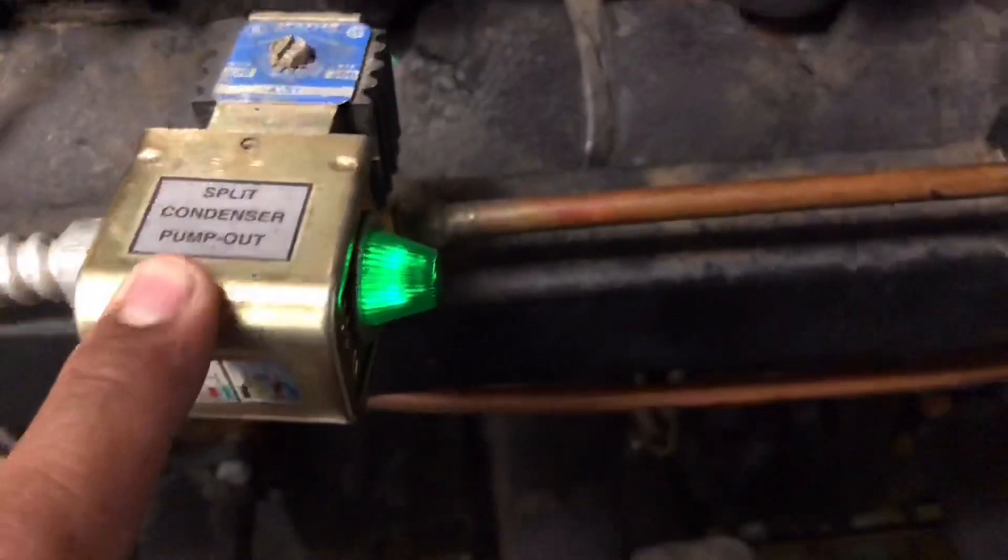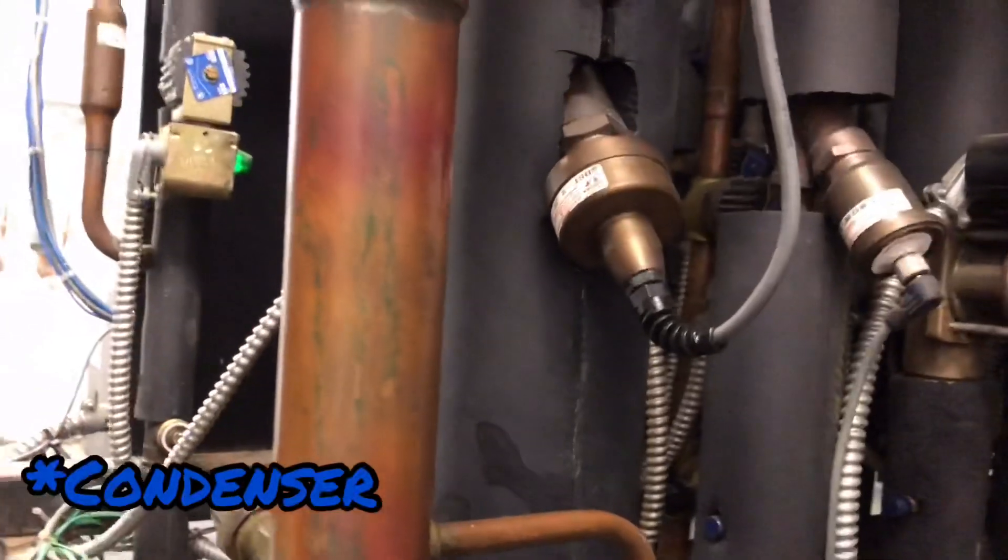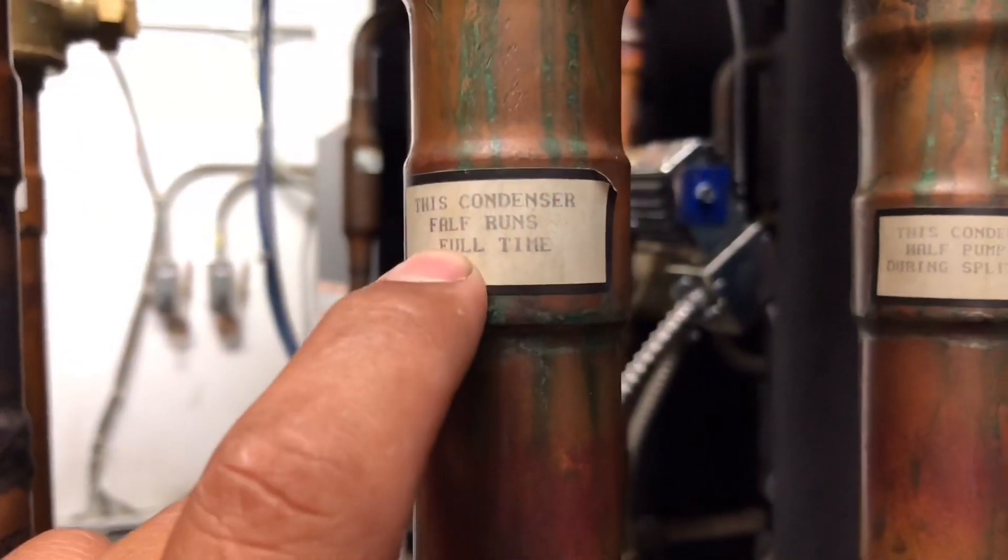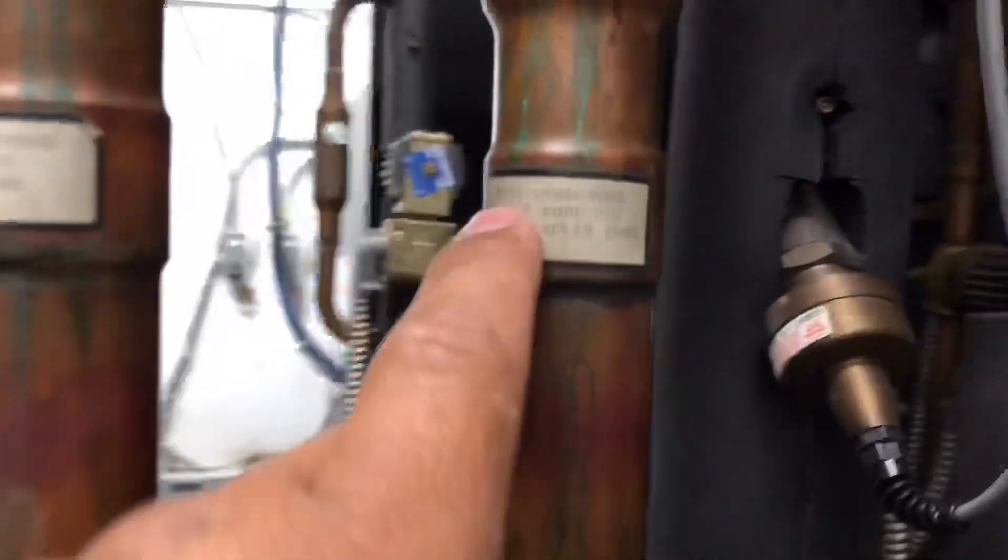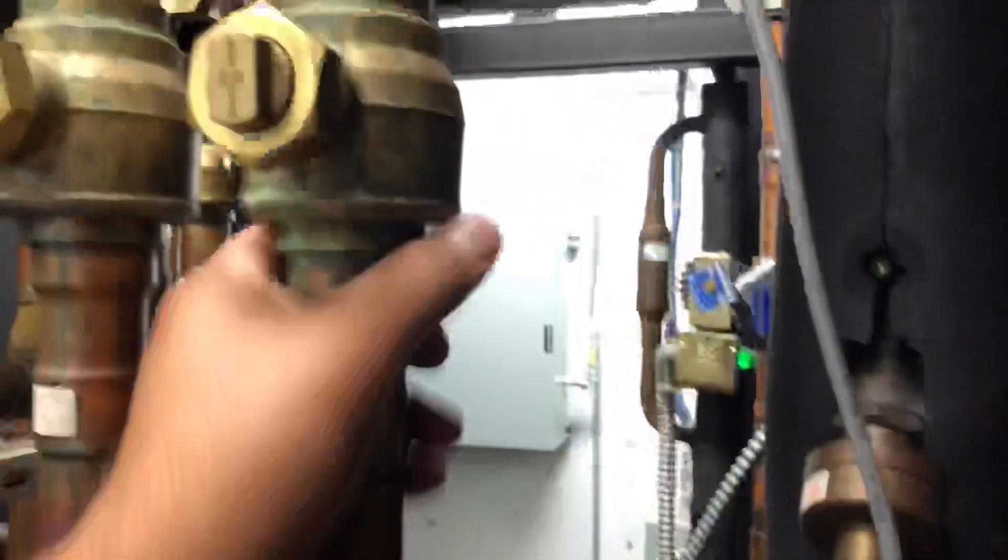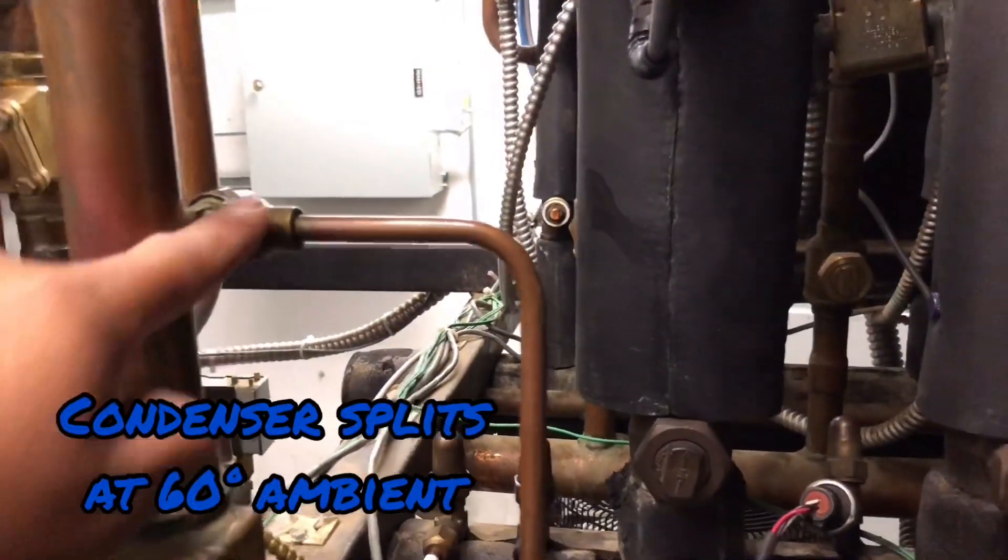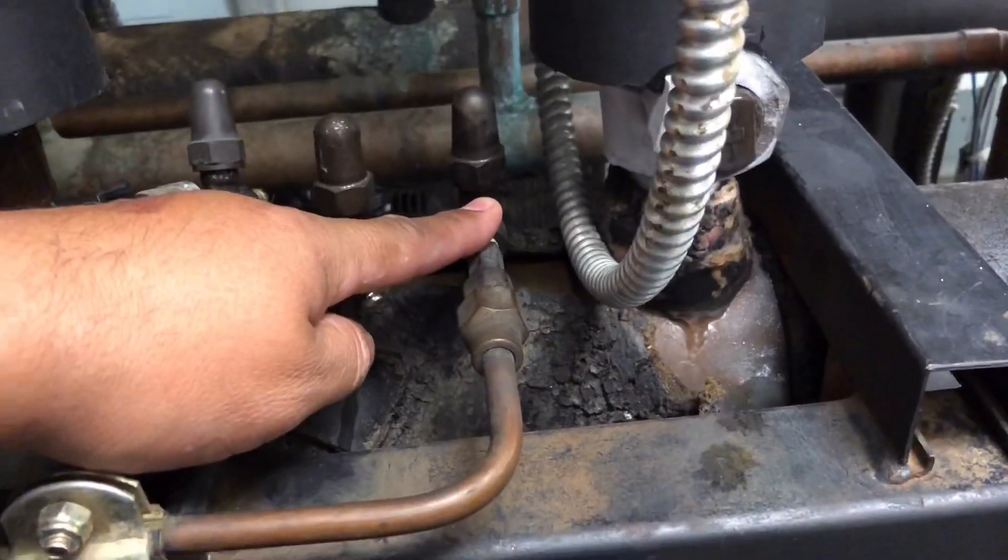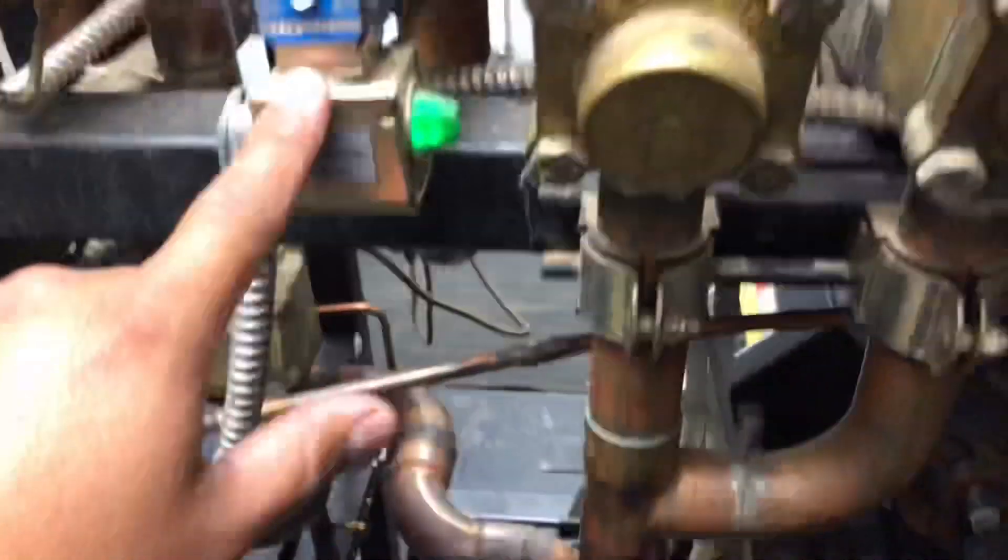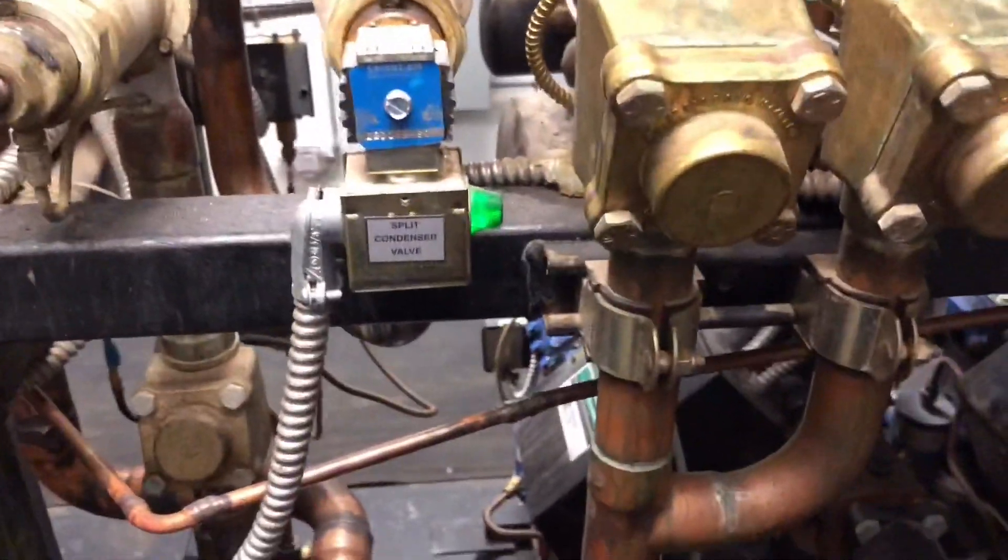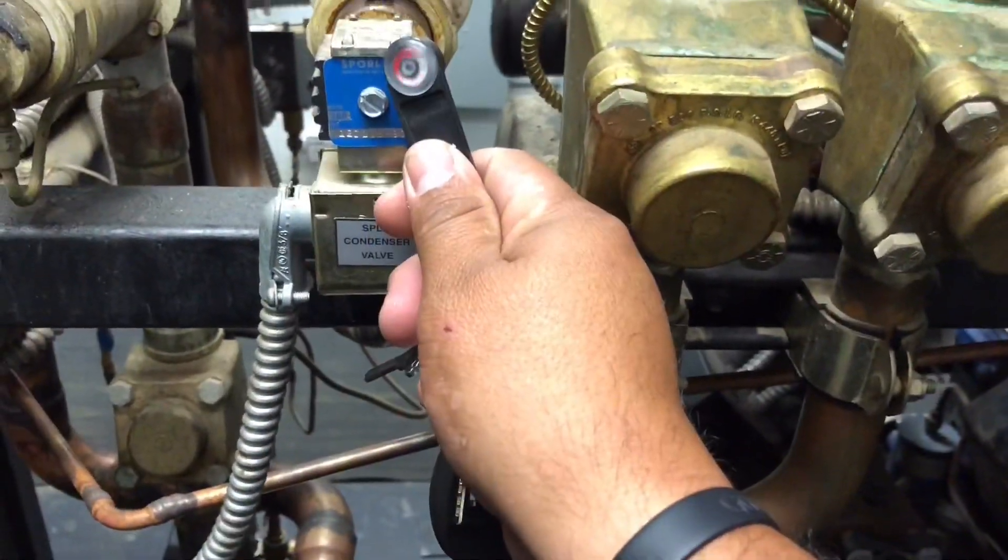That's my split condenser pump out. Right now we're only using half of the condenser. This condenser runs full-time, this condenser runs half. This side of the condenser is shut off and we're pumping out everything inside this condenser back into the suction line. We're pumping out half of the condenser back into the suction. As you can see, that valve's energized right here. The cold weather is doing some things.